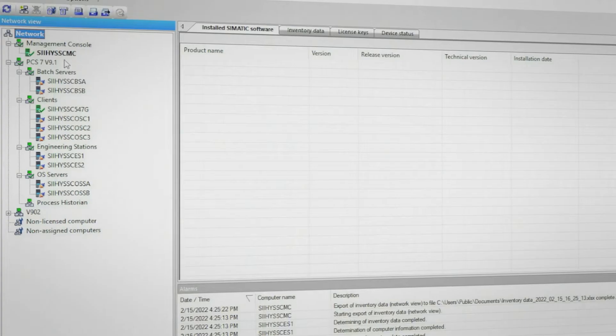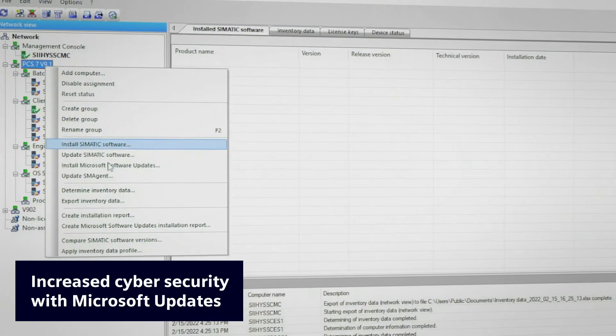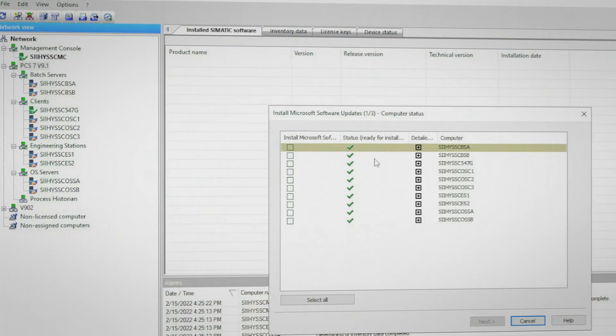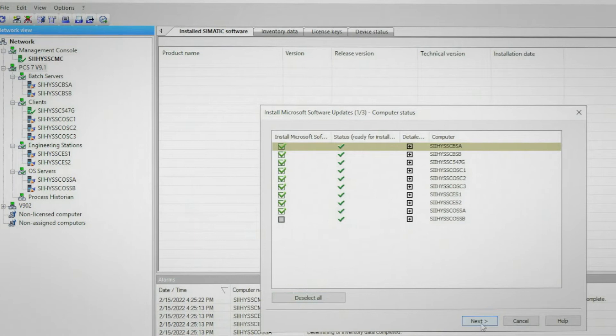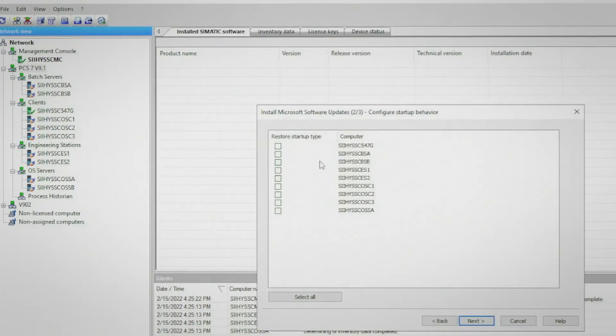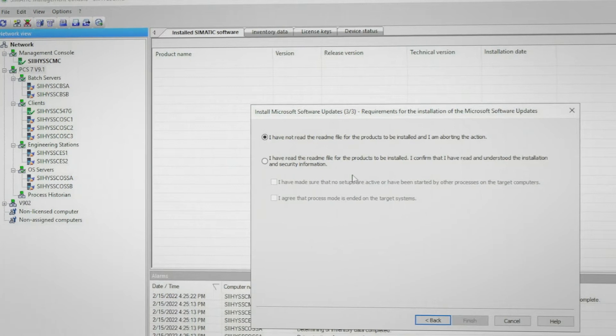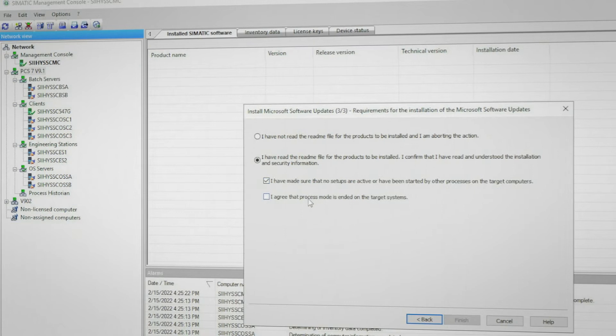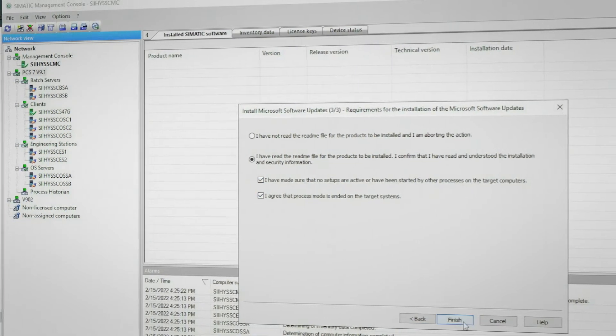As of PCS7 version 9.1, the management console allows the user to deploy Microsoft software update installations. The Microsoft software updates are remotely deployed from Windows Server Update Services to Windows Update agents on each target computer of the SIMATIC management console. This procedure follows the same set of steps used for the deployment of SIMATIC software updates. Information about already installed Microsoft software updates, as well as those that are currently being installed, are reported by the management console.